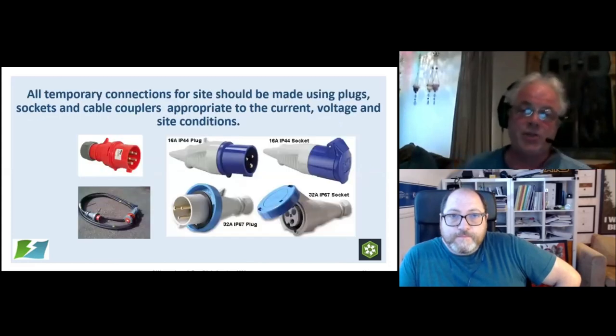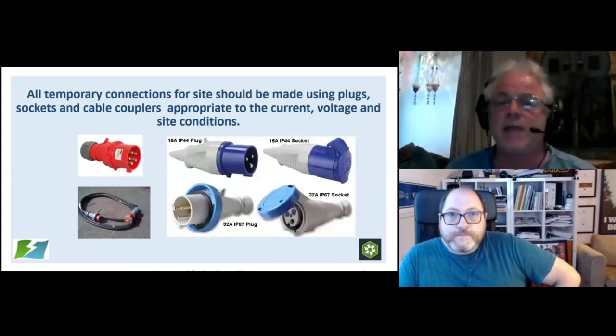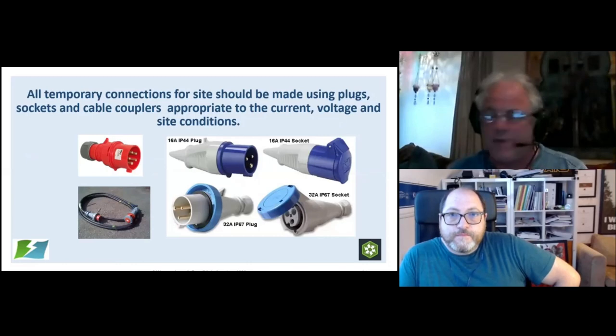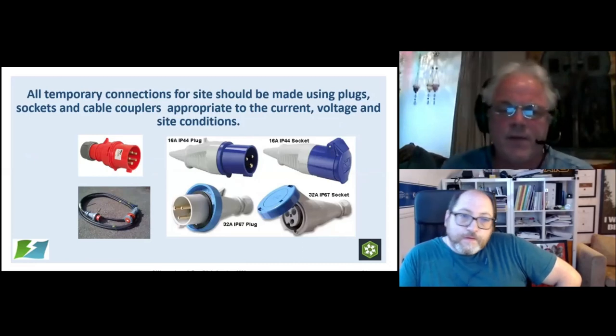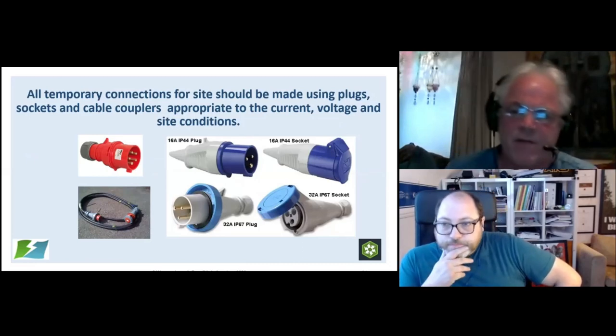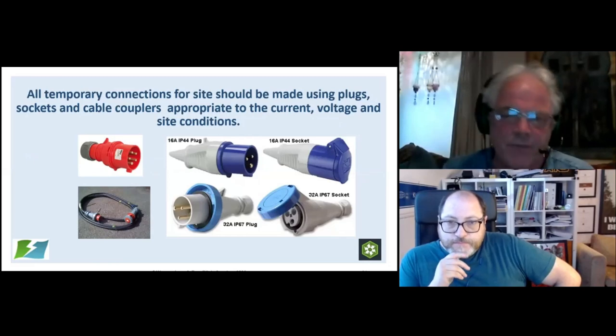All temporary connections should be made using plugs and sockets and cable couplers, which are appropriate to the current, the voltage, and the site conditions. The standard ones that we tend to use are the CEE form, 32 amp, 16 amp, 63 amp, 125 amp, single and three phase.